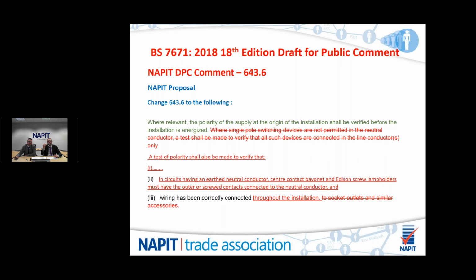It's the existing wording. Indent 2, in circuits having an earthed neutral conductor, centre contact bayonet and Edison screw lampholders must have the outer or screw contacts connected to the neutral conductor. We modify that wording because it's simpler and cleaner in this way. It's not quite so ambiguous as it was before. It could be taken as being slightly difficult or slightly confusing. Indent 3, wiring has been correctly connected throughout the installation. Polarity should be verified throughout the installation, not just the socket outlets and similar accessories. It should be throughout the installation.